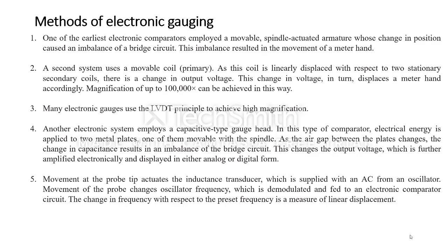Another electronic system employed with this comparator is capacitive change. Two metal plates which are movable — and this movement is connected to a spindle. With the spindle movement, the gap between these two metal plates will change, which changes the dielectric constant. With the change in the dielectric constant, the capacitance changes. This change in capacitance is connected to a bridge, which is similar to a Wheatstone bridge. This imbalance movement is connected to a meter, which varies linearly.